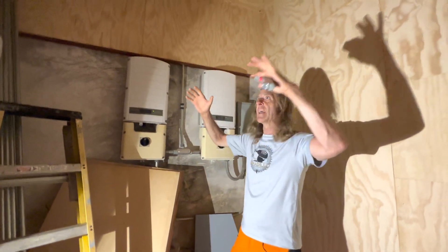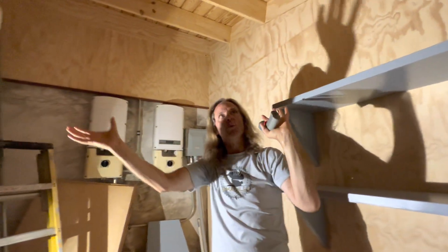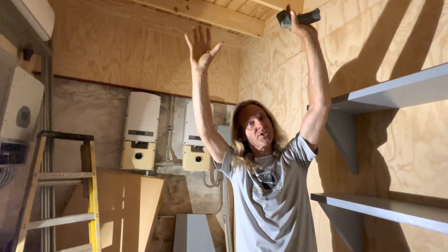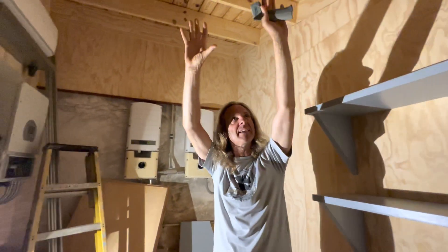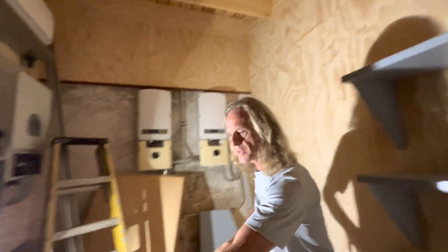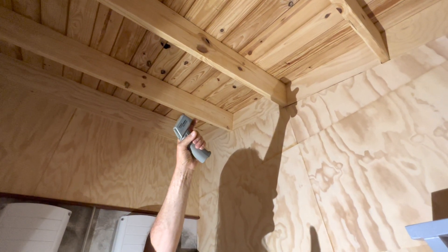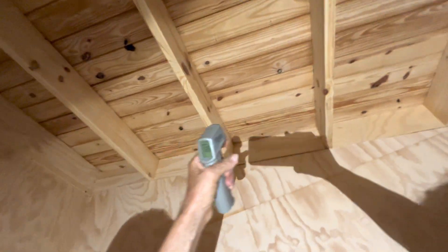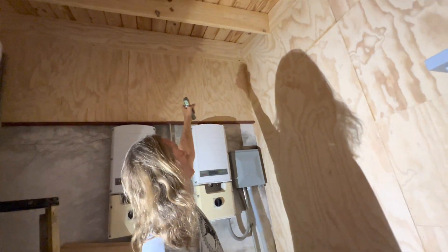78, 78, 77 degrees — this 77-degree concrete wall with the water behind it is a lot of thermal mass, and it's absorbing the heat from the rest of the building. There's an exterior wall reading 81 degrees. Even with insulation there's still a thermal load, and all the heat from the sun beating down on this roof and these walls is coming through — giving 81–82 degree walls. Higher up, the roof has four inches of polyisocyanurate insulation, so it reads 83 degrees, warmer right above the units.